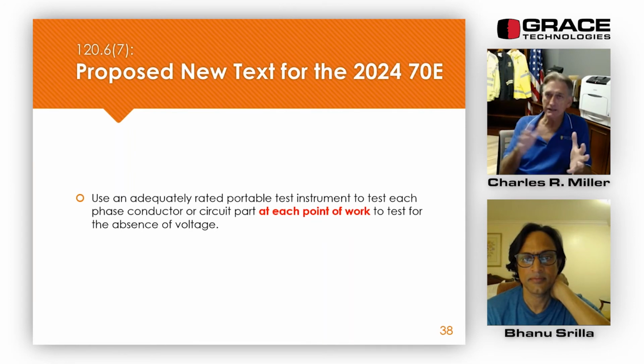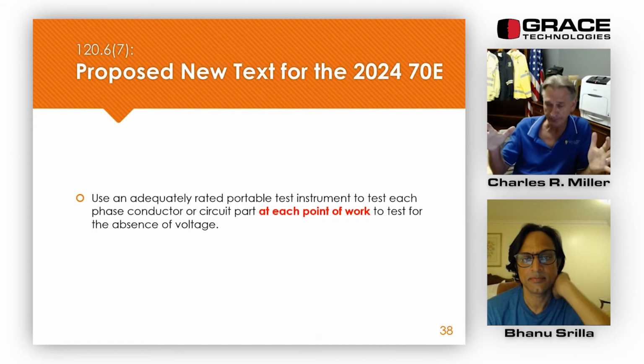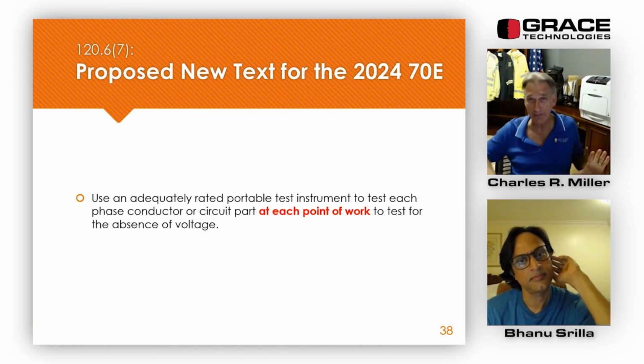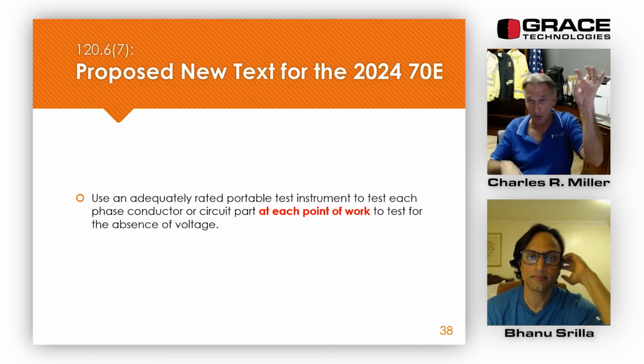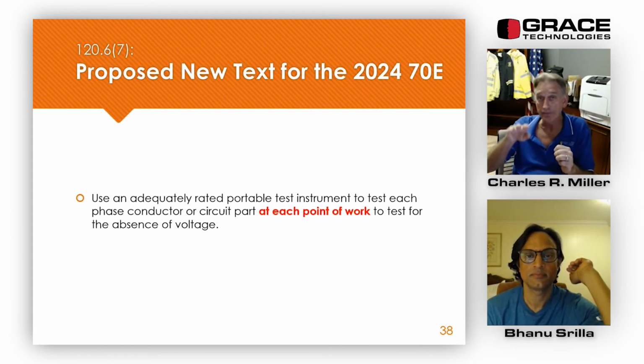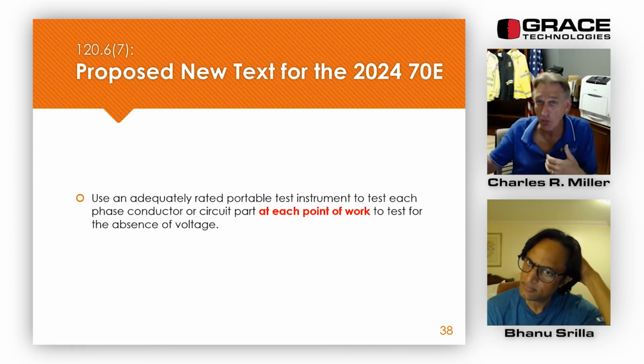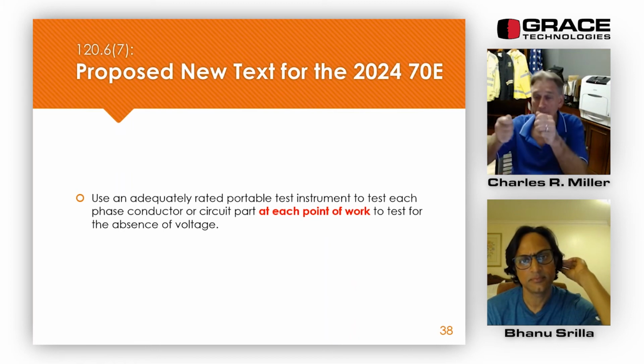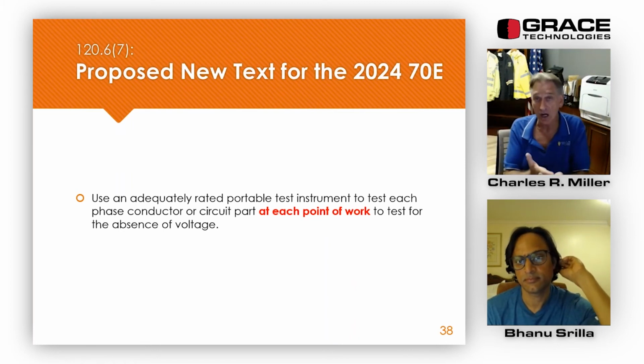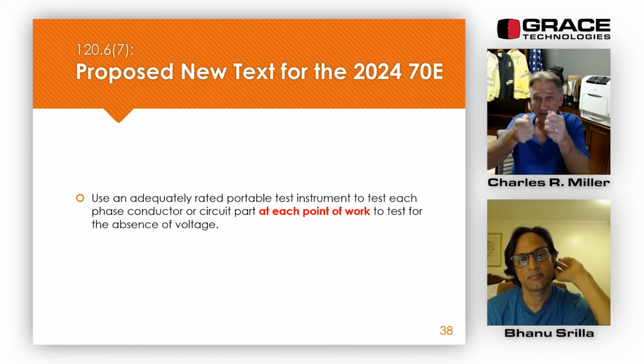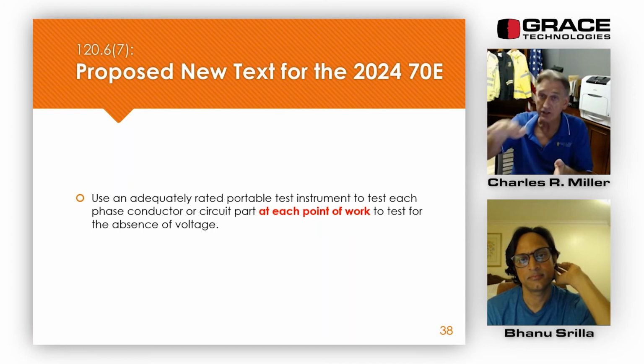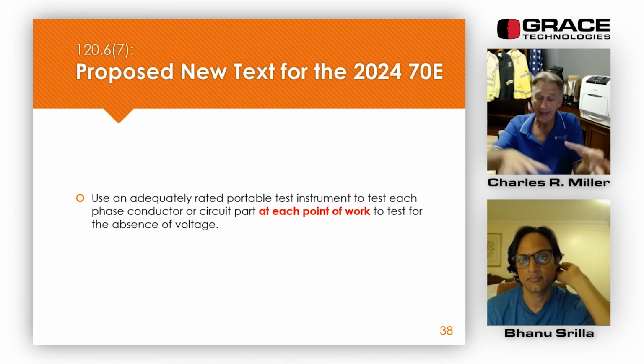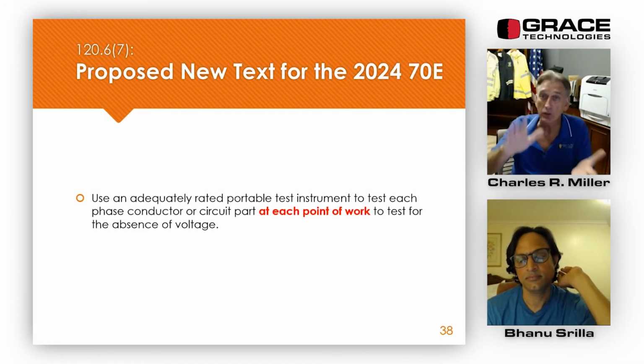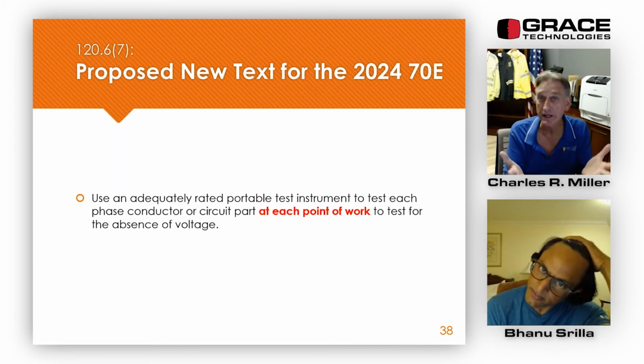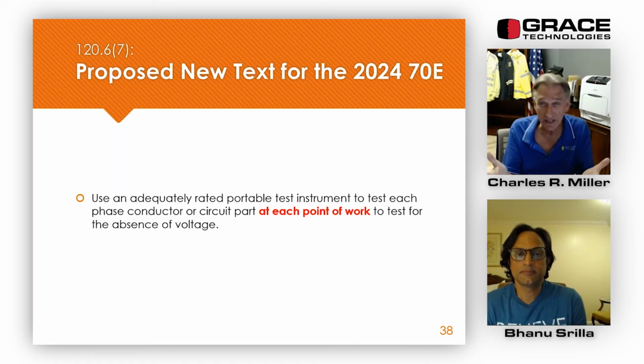All right, well, first glance, it sounds good, but there is no definition of, well, what does point of work mean? All right, in a cabinet, you turn the disconnect off for the whole cabinet, and typically it's the upper right corner, and you maybe even lock it out, you turn it off before it gets there. On the line side, you open the cabinet up, you're what I call dressed out, you have shock protection, arc flash protection, and you test your meter, test for the absence of voltage at the top, and then test your meter again. Then you could take off your PPE and work on or do anything in there, because the equipment is in an electrically safe work condition, as long as you've gone through all the 7 or 8 steps necessary.